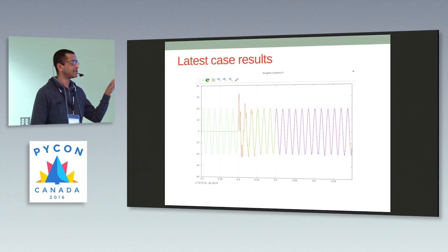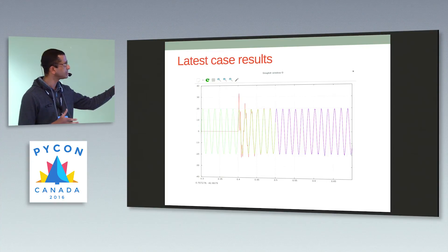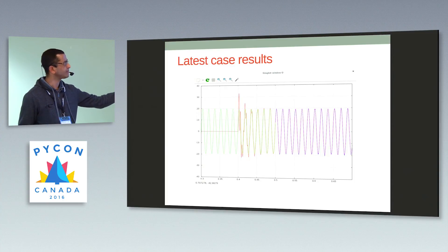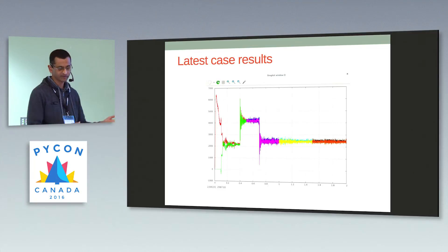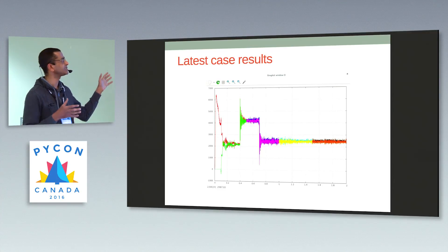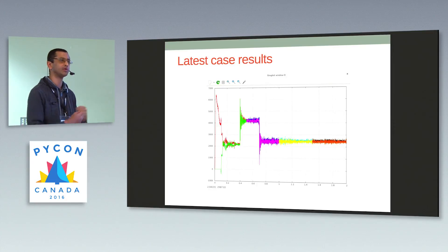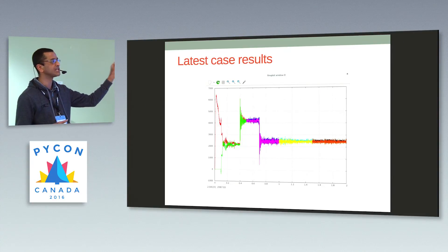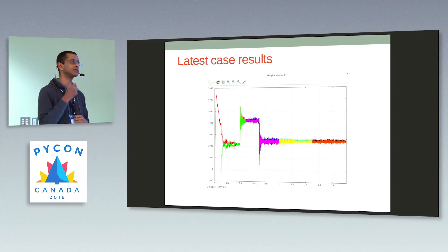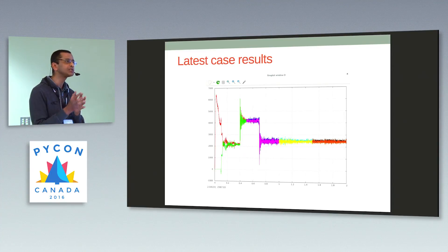These are the currents that two inverters are supplying. The idea is to share power equally. At 0.4 seconds another inverter is switched on, and very soon these two currents merge — which means they are actually sharing power equally. The power supplied by the two inverters also shows that at different points in time, as the load changes and power demand changes, the two inverters continue to share power equally. This works because the control gains are designed so that these two controllers merge together at all times.